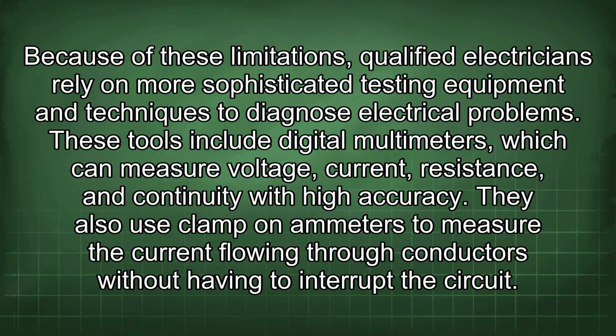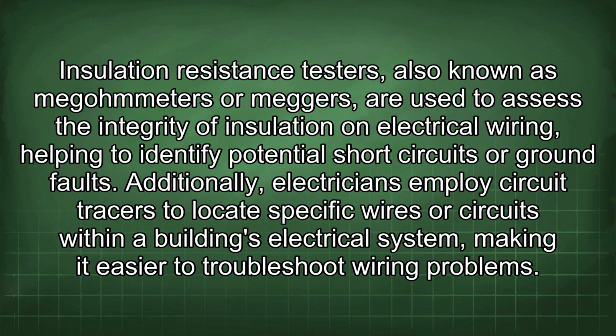These tools include digital multimeters, which can measure voltage, current, resistance, and continuity with high accuracy. They also use clamp-on ammeters to measure the current flowing through conductors without having to interrupt the circuit. Insulation resistance testers, also known as megohmmeters or meggers, are used to assess the integrity of insulation on electrical wiring, helping to identify potential short circuits or ground faults.